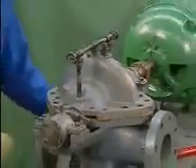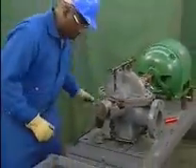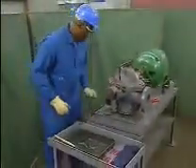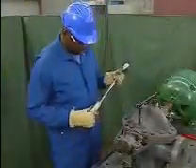After the upper half of the pump casing is in place, the mechanic prepares to install the bolts that hold the casing together. He first cleans the bolts and then applies a lubricant to them so that they will thread easily. He partially tightens the bolts by hand and uses a torque wrench to completely tighten the bolts to the torque value specified by the pump manufacturer.